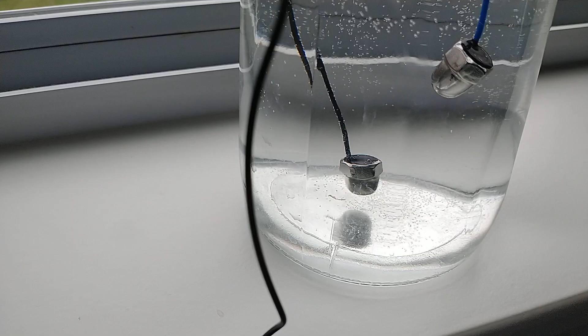So you want to set it maybe halfway in your overhead tank. Put the yellow one halfway, so that as soon as it goes below half, you can start pumping again. You don't want to put it too high, close to the red one, because then the pump keeps pumping on and off, which is not good.